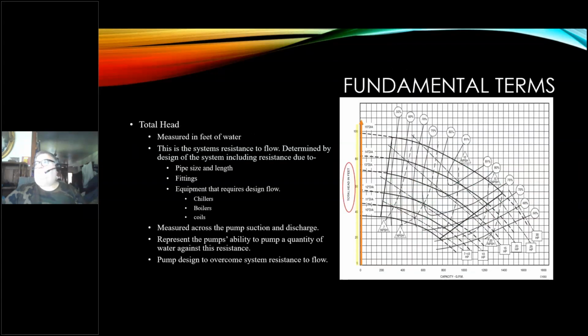The vertical line represents the total head in feet. It increases from 0 at the bottom all the way up, and in this case we're just below 100 feet at the 15-inch diameter curve. It's measured in feet of water. You can get these in metric also. This is the system's resistance to flow, determined by the design of the system, including resistance due to the pipe size and length, the fittings, and the equipment that requires design flow, like chillers, boilers, and coils. It's measured across the pump suction and discharge right at the pump.